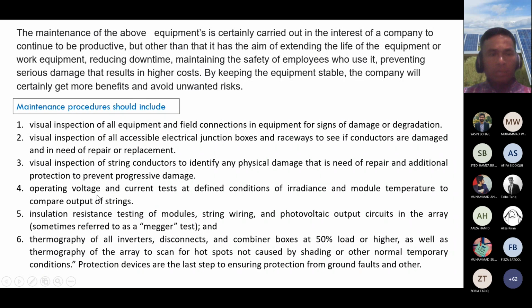And also we do the checking of operating voltage and current. So for every equipment we need to check the operating voltage, especially for the strings, and we also do testing. We even need to use the thermal imager just to make sure there is no overcurrent on any one string. This can happen and damage the string, and can even cause a fire.